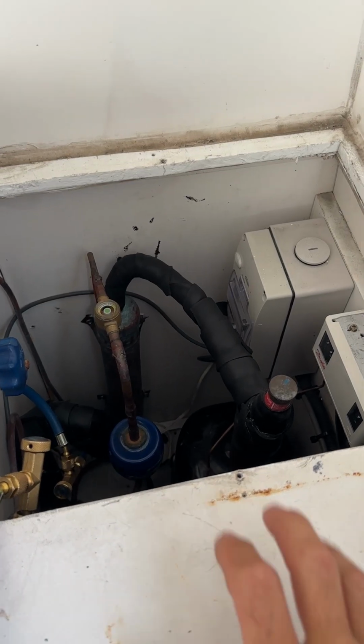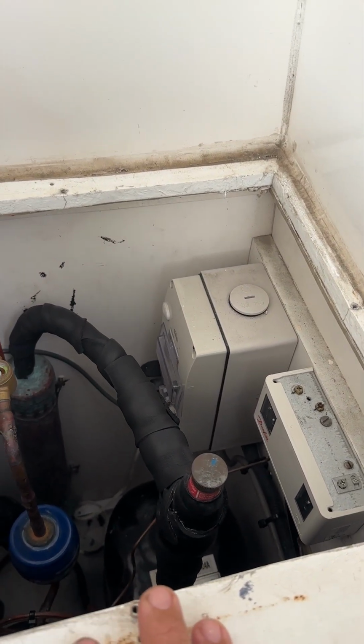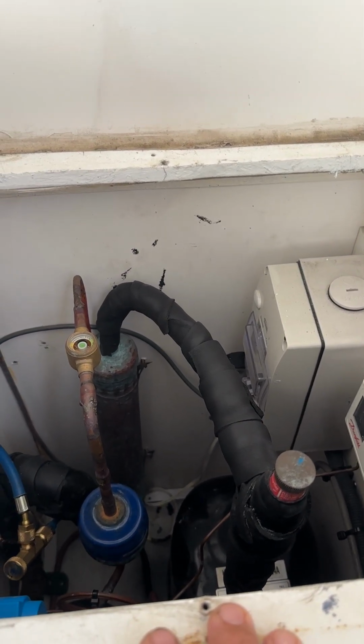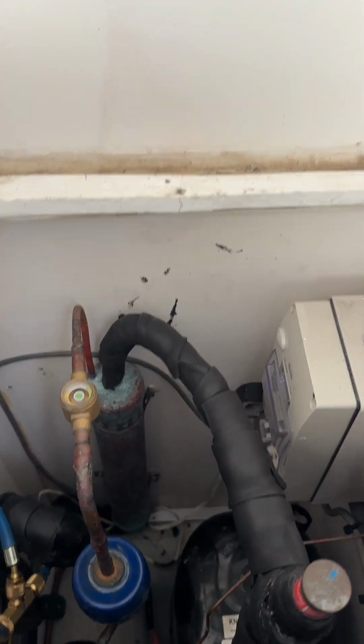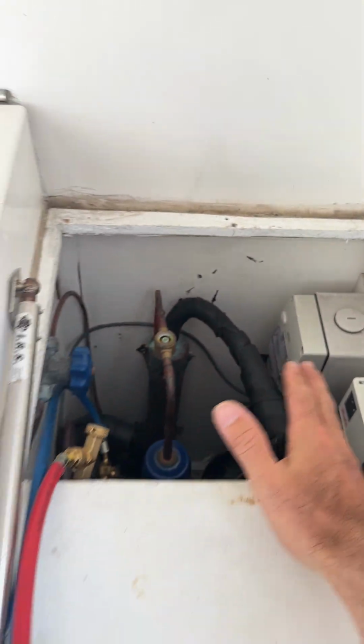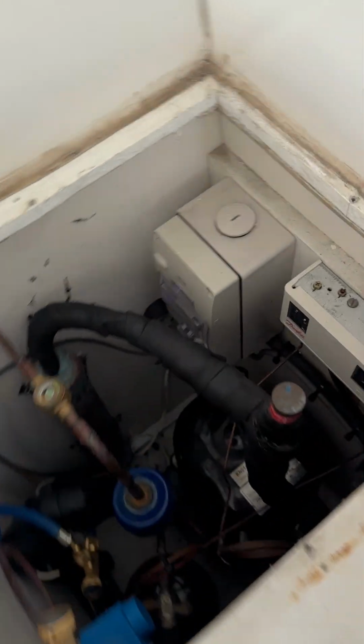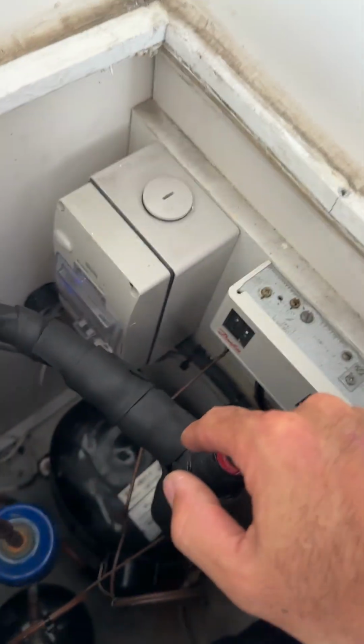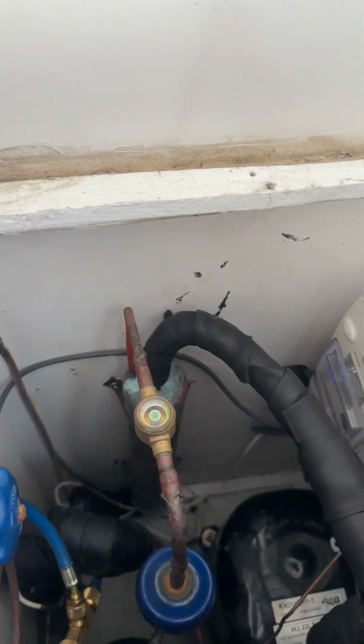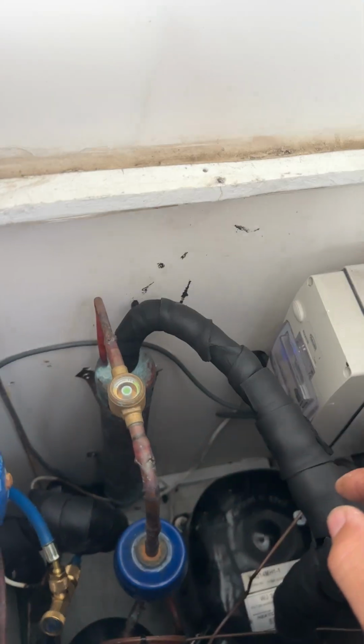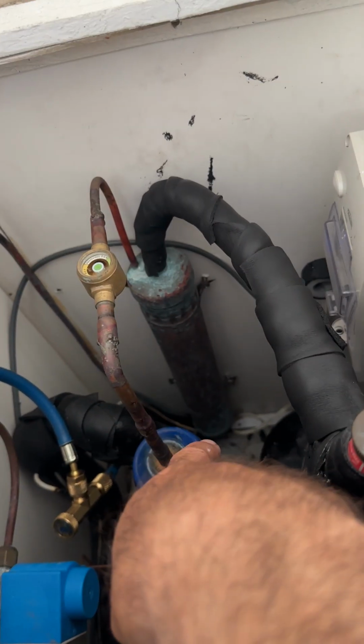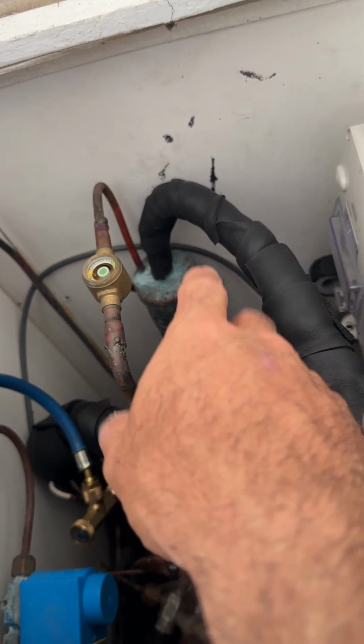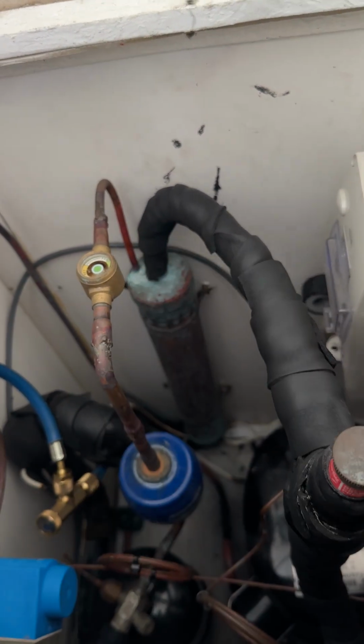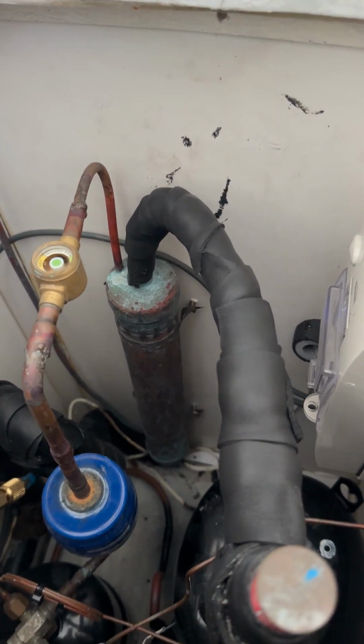This is more of a follow-up video from another video I did about refrigerant heat exchangers or liquid suction heat exchangers. So this is actually a low temp freeze system. It's got two eutectic plates in it with a reasonably sized compressor in there. And this is actually running on R404, and there's your refrigerant heat exchanger or liquid suction heat exchanger. So this is an example of it in situ.